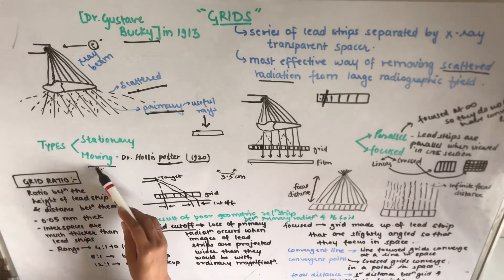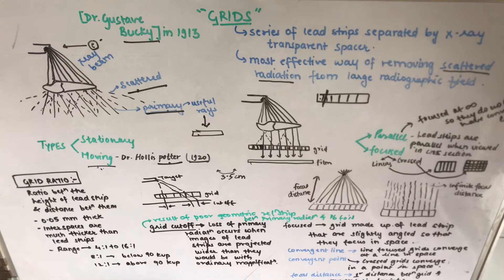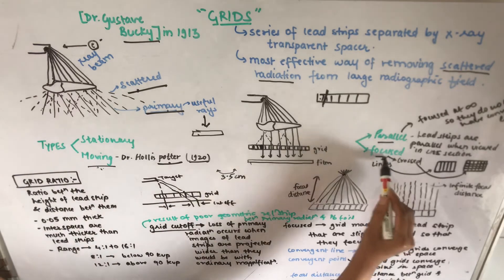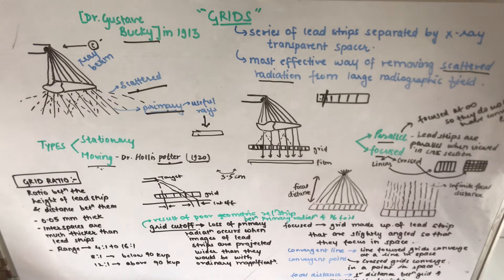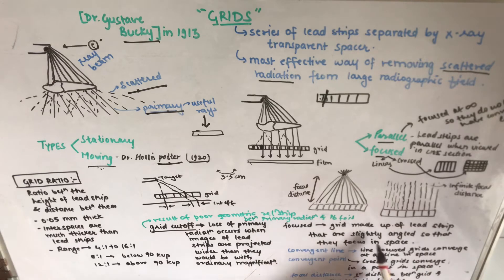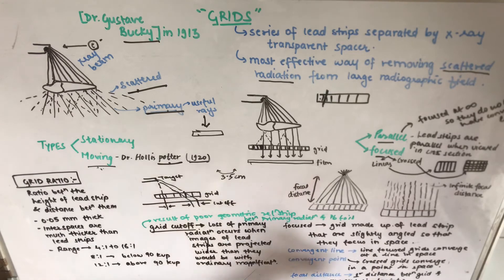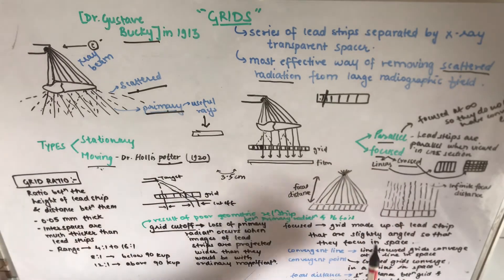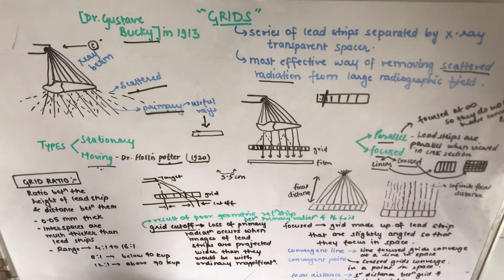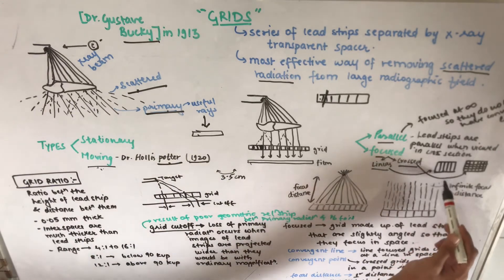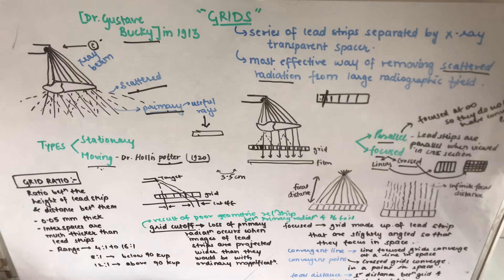There are also parallel and focused types of grids. Focused grids are made up of lead strips that are slightly angled so that they converge in space. Within focused grids, there is the linear type, in which the lead strips are parallel to each other along the longitudinal axis. This allows the x-ray tube to be angled along the length of the grid without loss of primary radiation due to grid cutoff.